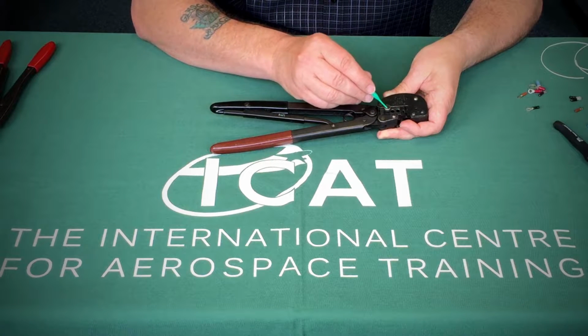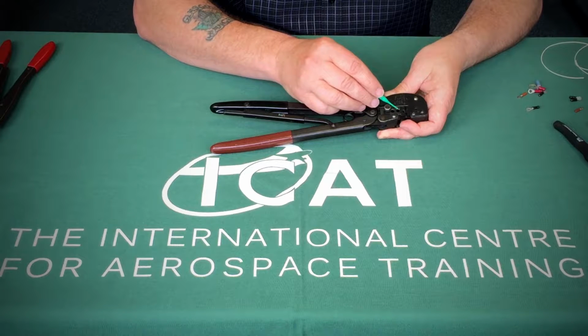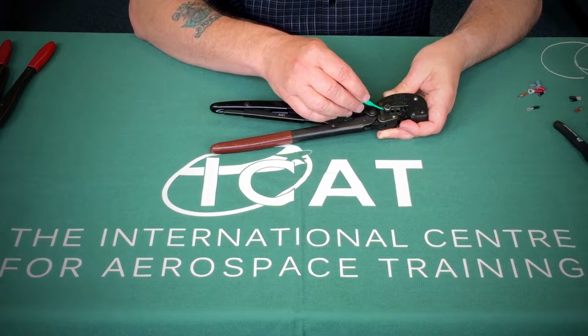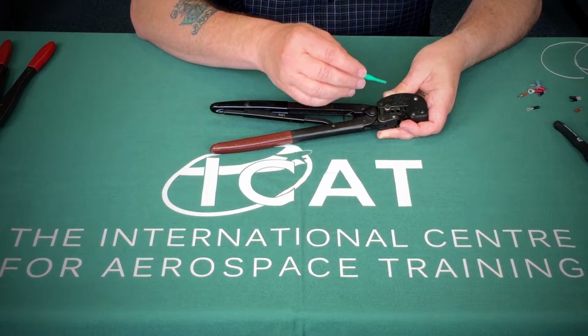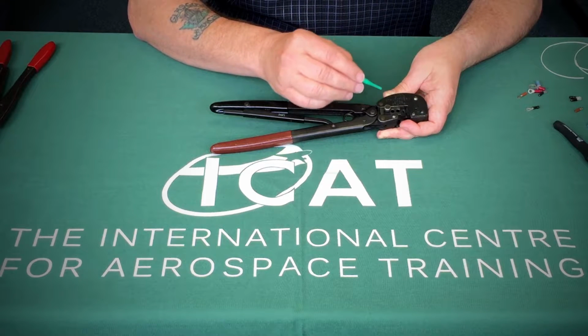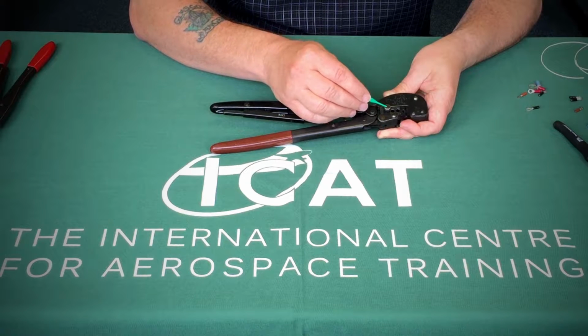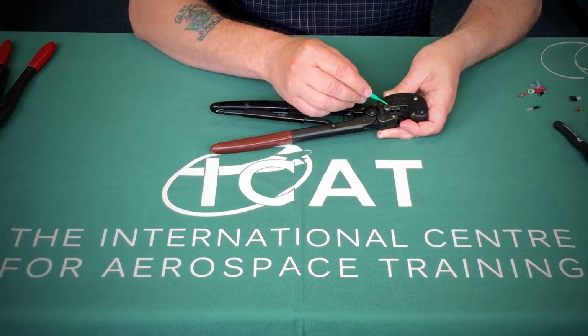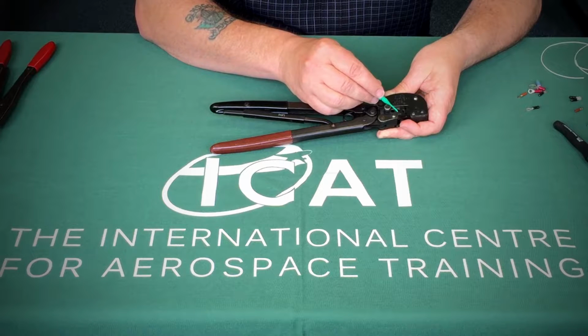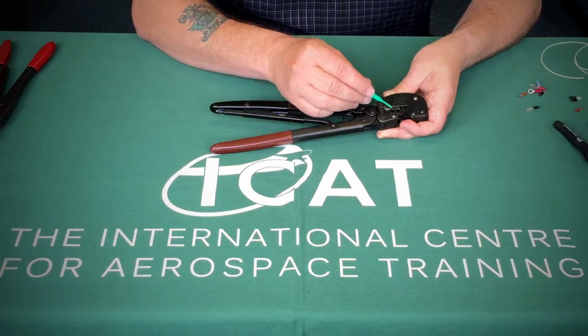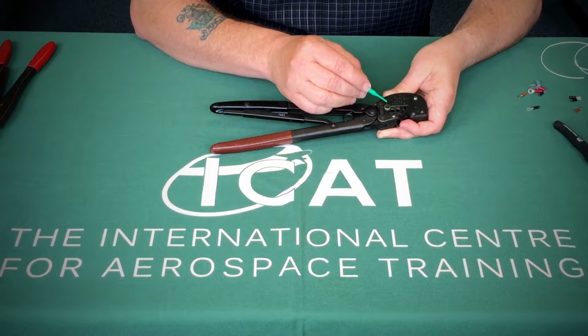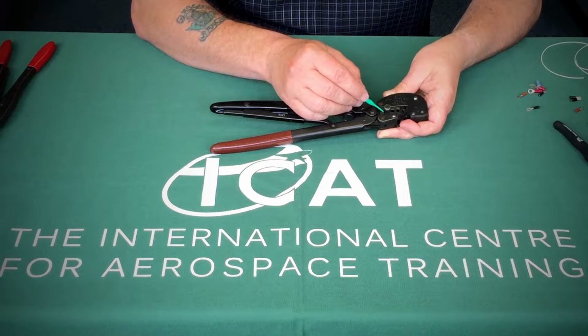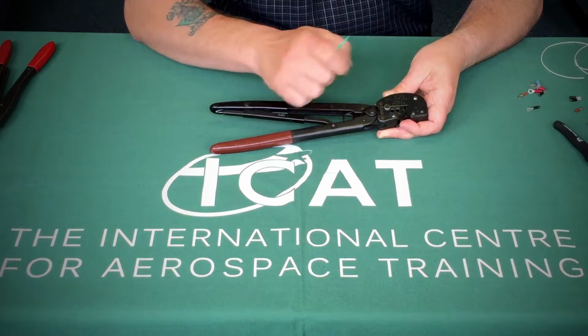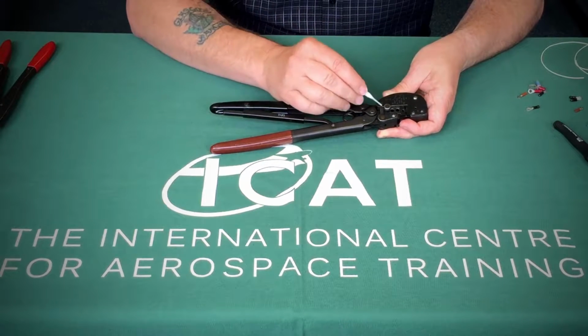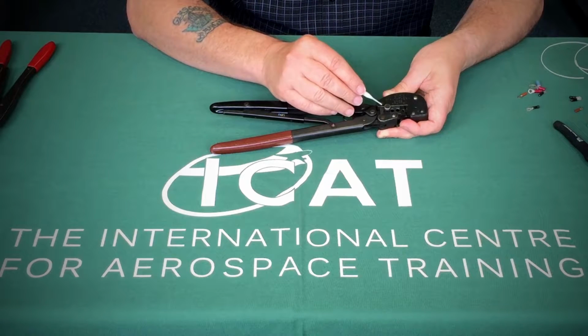Other things to note is this 3-position pin here. This allows me to select this tool for use on the same size cables, but may have different levels of insulation thickness. In position 3, where it is at the minute, it can be used with thicker insulation, and I can move it to position 1 if the cable has a thinner insulation. Now, information on which setting to set it on should be detailed within your standard wiring practices manual. However, if you're unsure, we can do a test crimp, which we'll go through in a minute, to see whether the insulation is being supported correctly.